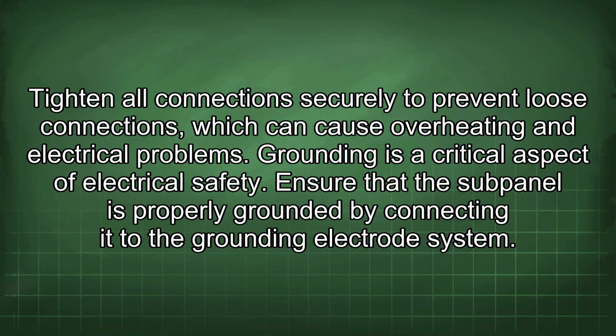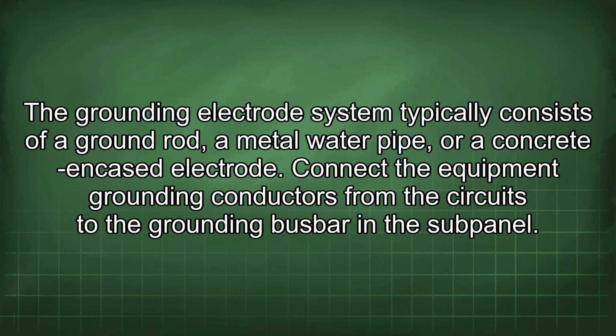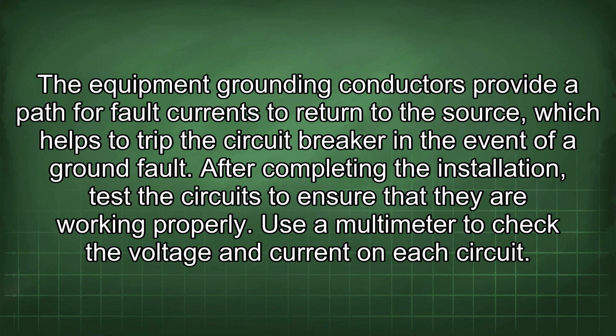Grounding is a critical aspect of electrical safety. Ensure that the subpanel is properly grounded by connecting it to the grounding electrode system. The grounding electrode system typically consists of a ground rod, a metal water pipe, or a concrete-encased electrode. Connect the equipment grounding conductors from the circuits to the grounding busbar in the subpanel. The equipment grounding conductors provide a path for fault currents to return to the source, which helps to trip the circuit breaker in the event of a ground fault.